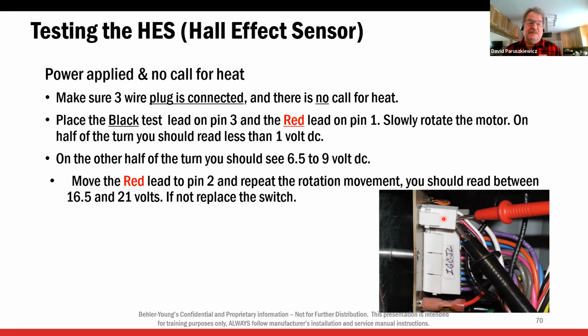It generates a DC voltage and sends it back to the board to tell the board that yes, indeed, the inducer is not just running, but it's running at the proper speed. All right, so this is how we would test it. Again, you're going to get this on a paper form because there still are a bunch of the Hall effect sensors out there. It is not a switch. So when you see the 3 wires coming off the back of the inducer, that's a Hall effect sensor.